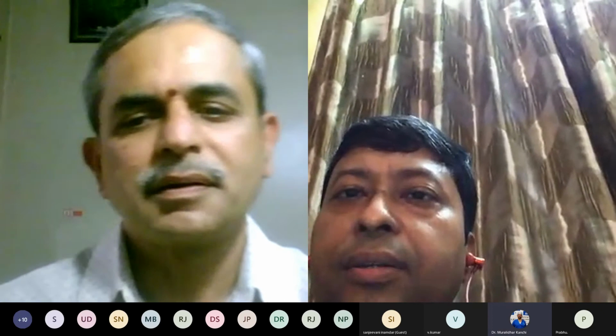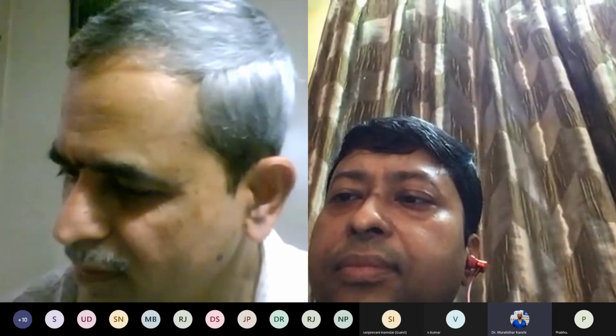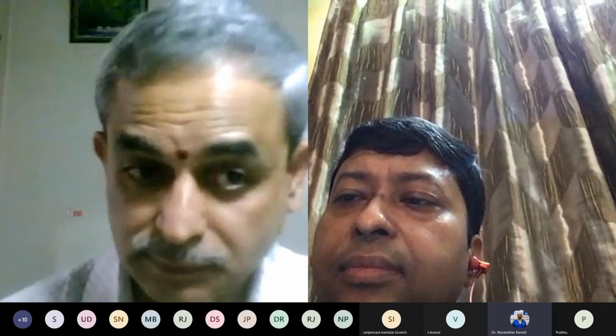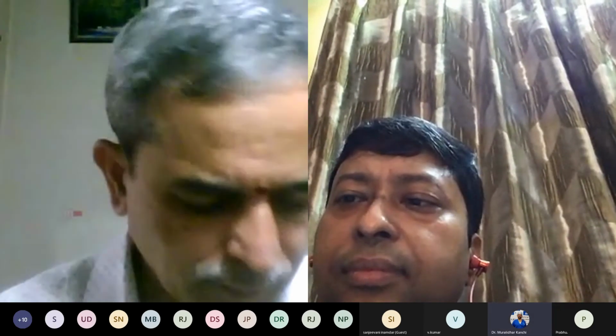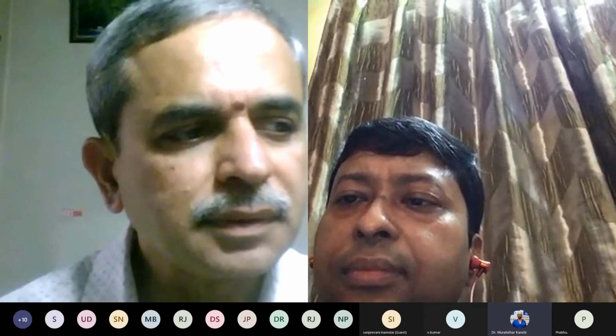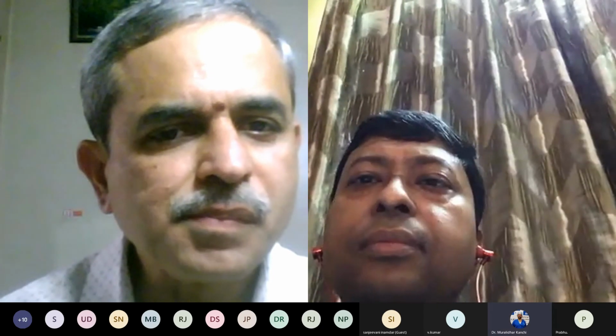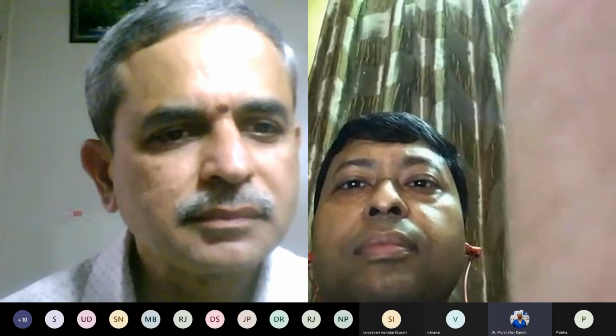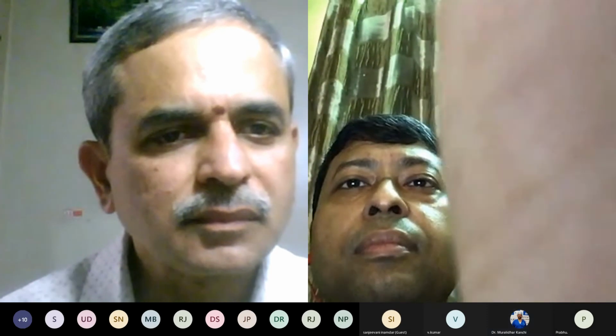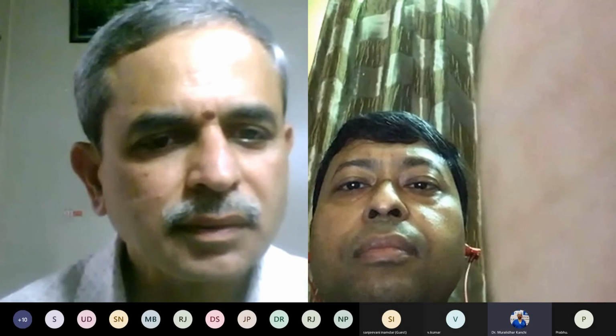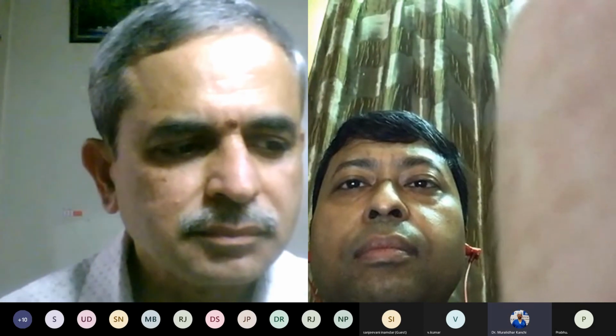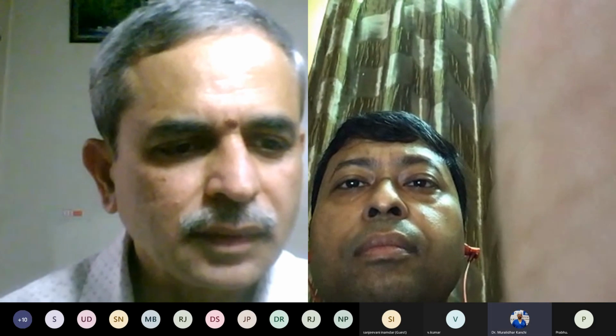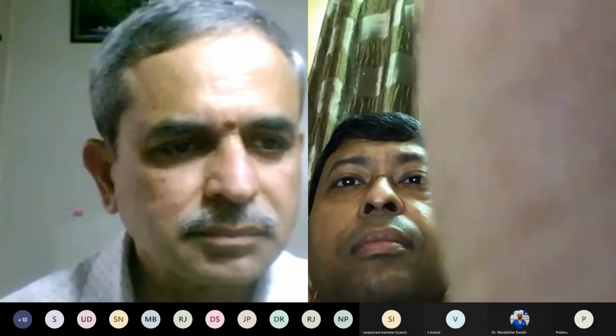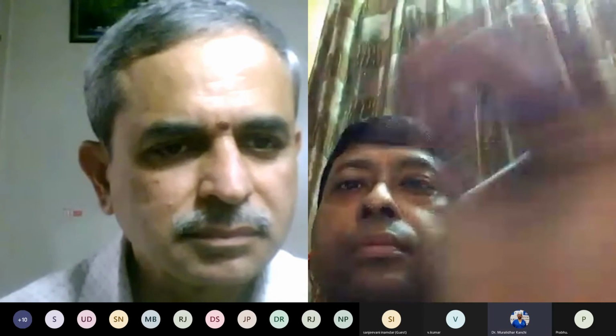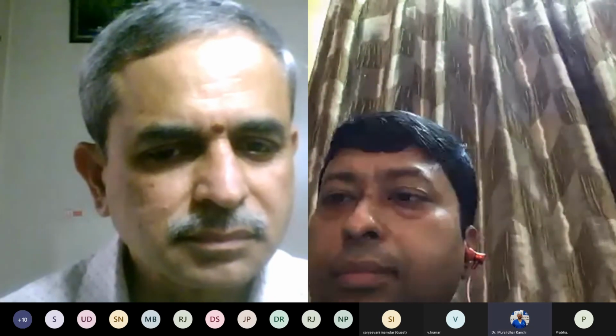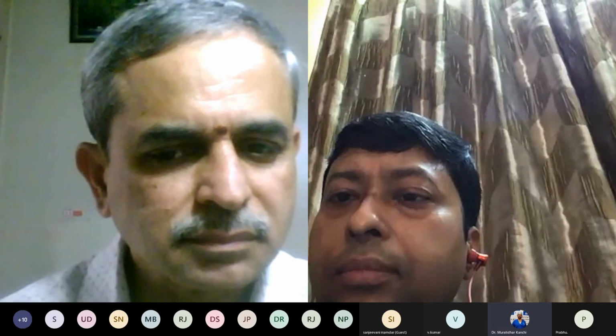Yes. To put it simplistically, the Nyquist limit represents the maximum Doppler shift frequency that can be correctly measured without leading to aliasing, and it usually equals the pulse repetition frequency divided by 2. And it is not fixed in a machine. The operator can alter it depending upon what the situation demands, as you correctly said. So this is an important component, especially in pulse wave Doppler, to exactly determine the speed, direction and velocity of flow, especially when it is low velocity flow.